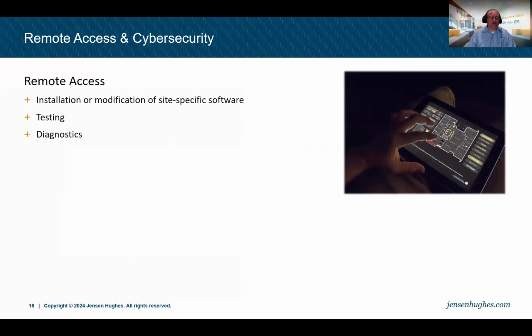Now, many organizations are doing some form of remote accessing of fire alarm systems, whether that's installation or modifications to site-specific hardware or firmware, software, even doing remote testing, doing diagnostics, maybe seeing what's wrong with the system before you respond to a site. There are all kinds of challenges, right, when it comes to fire alarm system installation, maintenance, and testing. Vendors may have inadequate staffing. There may be physical distance between a vendor's shop and a protected premise. Travel costs, just travel time. In some very large, congested cities like Atlanta, New York, San Francisco, it can take a very long time to get to a client site.